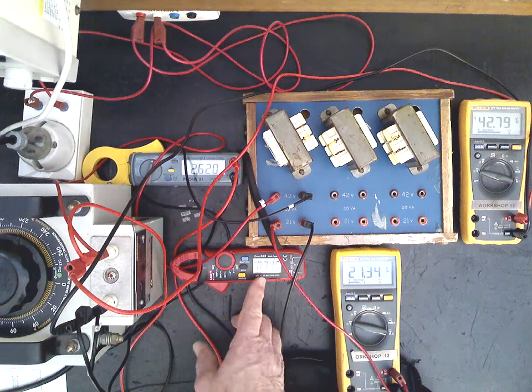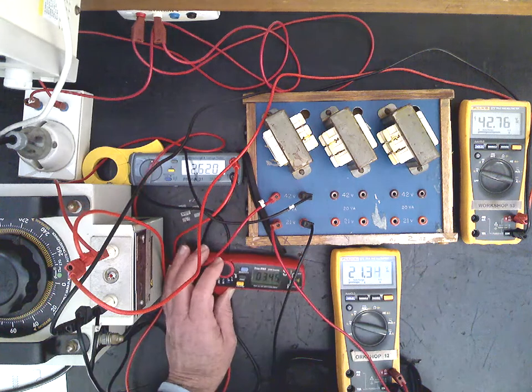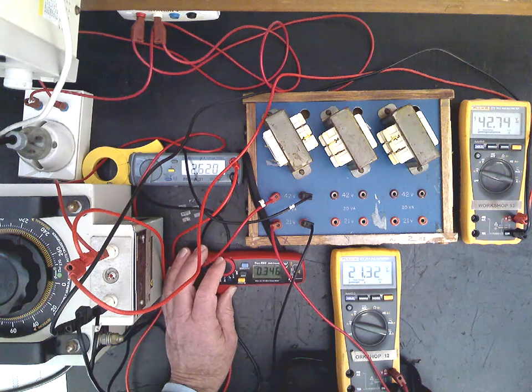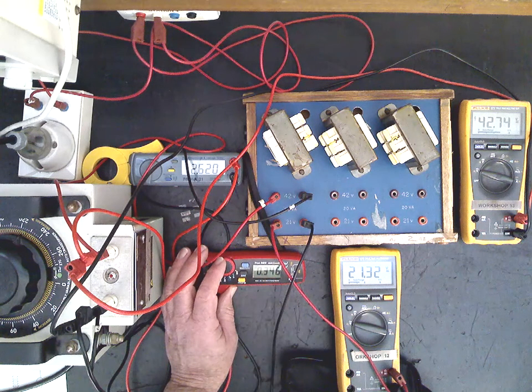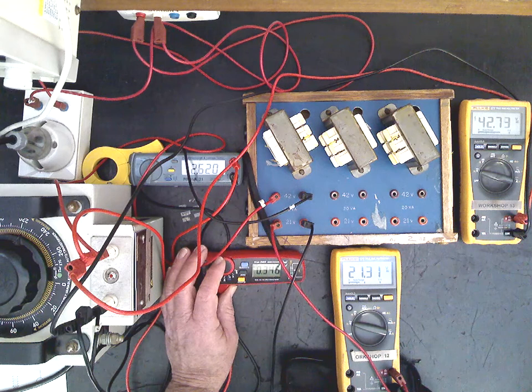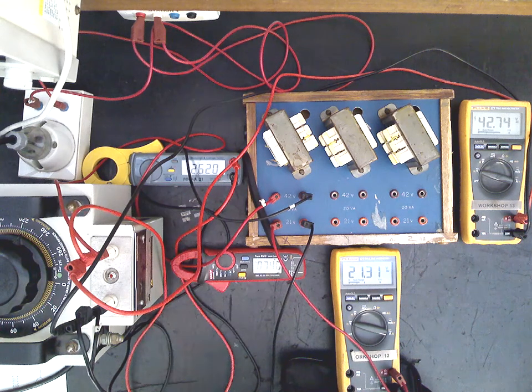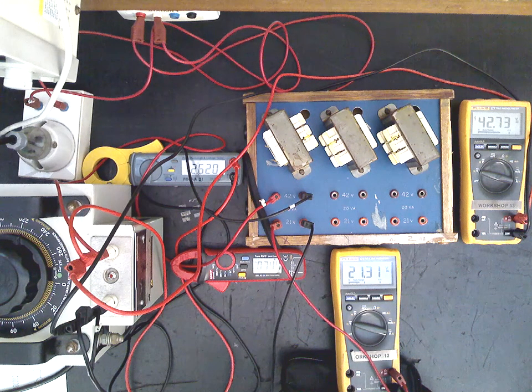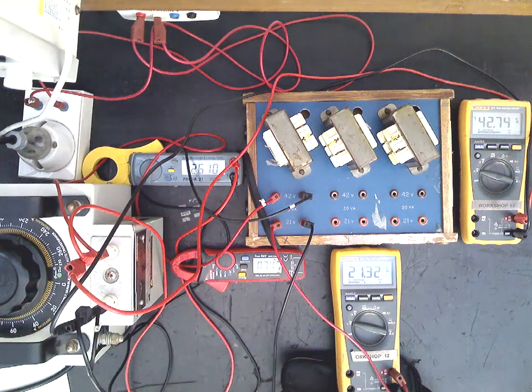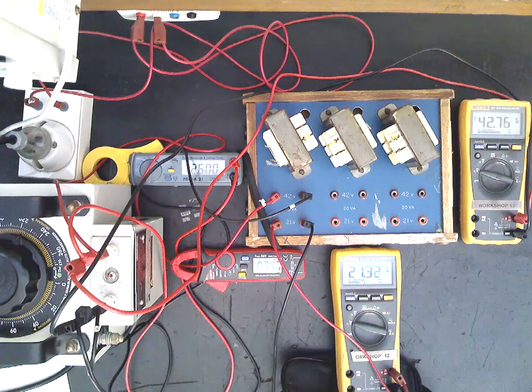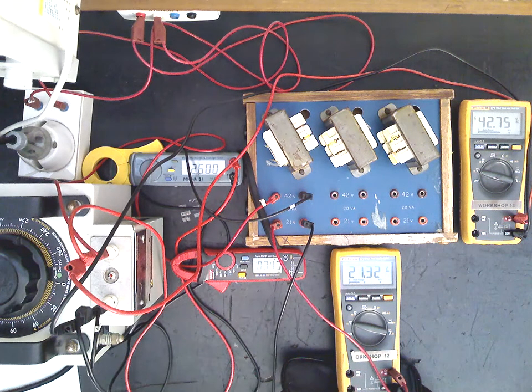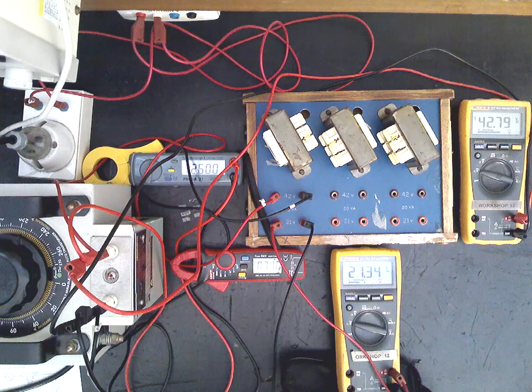The current in the primary is 0.35, 0.346, which is about 350 milliamps, 346. And then we can record those details and we'll be able to work out the efficiency of the transformer once we get the copper loss on the next test.